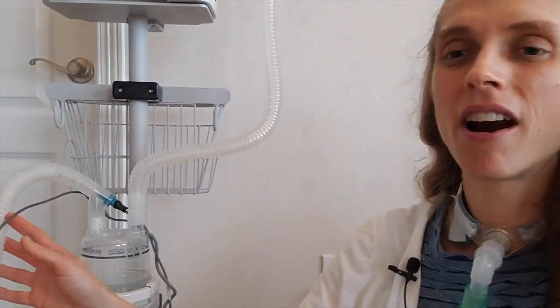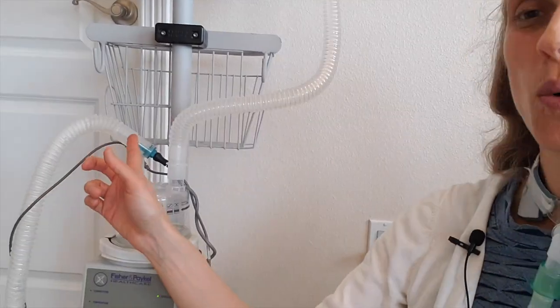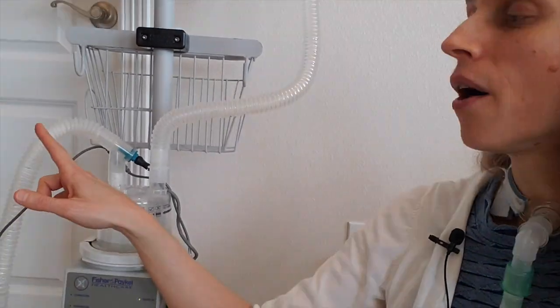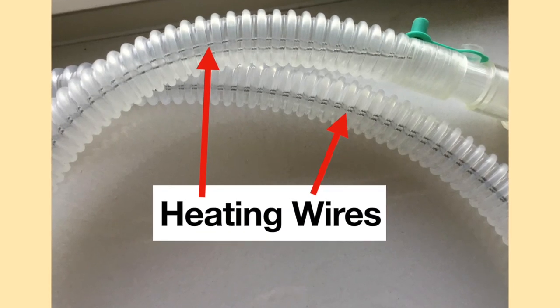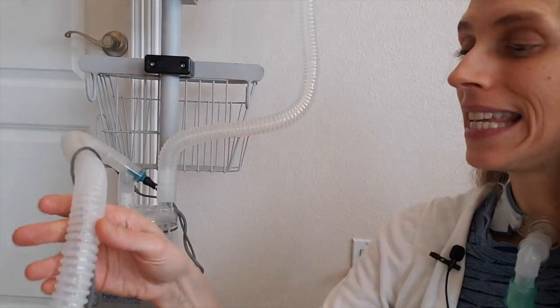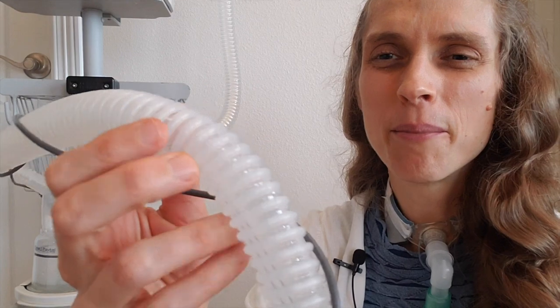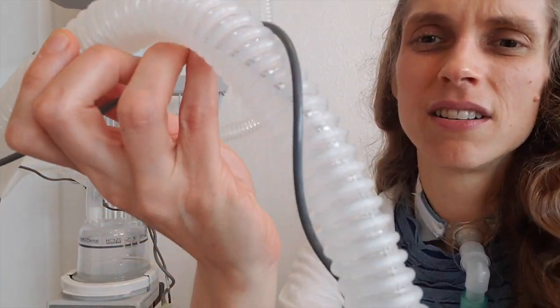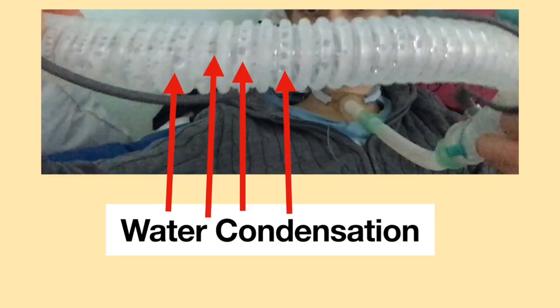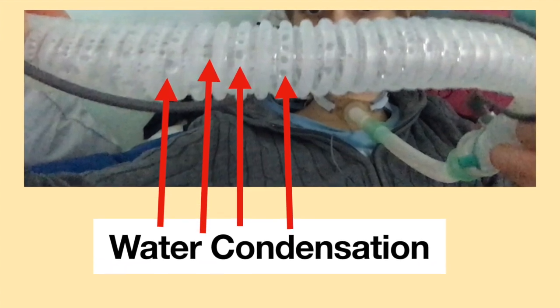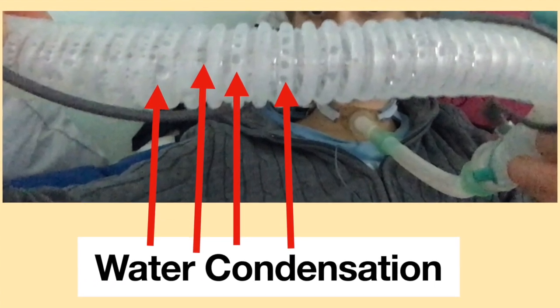And this is called a heated wire system because there are wires here. These wires go into the tubing. The tubing actually has wires inside. And so this tubing is heated up. Why do you do this? Because as you can probably see, there is some moisture in here. Can't see it that well. But there is some moisture in here, and as this air travels, it will start to cool down, and if it cools down, it starts to produce condensation because as the air cools, it loses the ability to hold water.